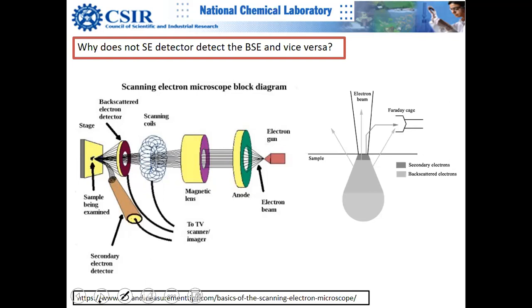Why does the secondary electron detector not detect backscattered electrons and vice versa? The secondary electron detector is at the side, and backscattered electrons are ejected with much higher velocity. By virtue of their higher velocity, backscattered electrons are more likely to travel straight and are less likely to be deflected toward the SE detector by the positive voltage.